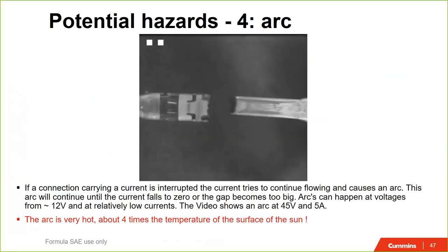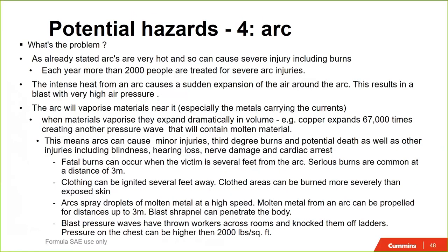Initially, arcs are very hot, somewhere around 4 times the temperature of the sun. You don't really want to be over it when it happens. For those of you in the room, if you look at the screen, you can see on the spade connector there's a portion that used to be straight across the base of that tip. That metal has vaporized as part of that arc. I have done some teardowns and failure analysis of some big gen sets where I've seen arc flashes on stators and rotors punch through a 1-inch thick steel casing. It's a real hazard.